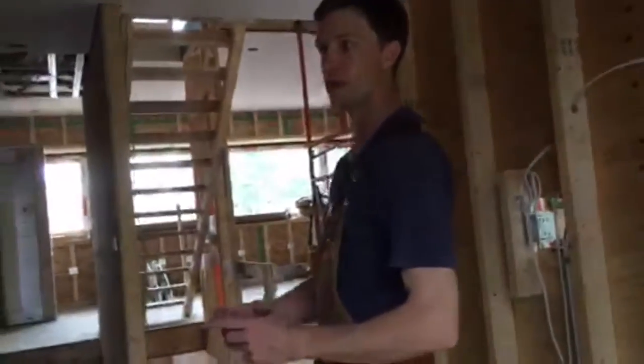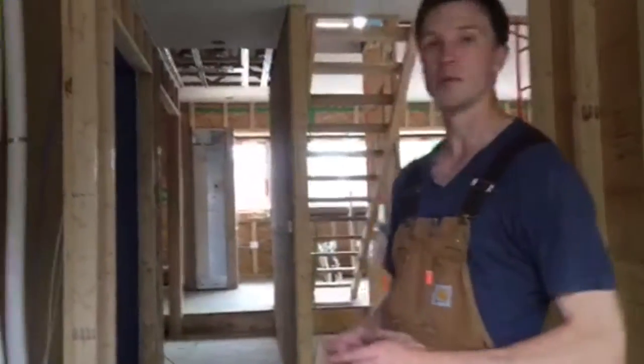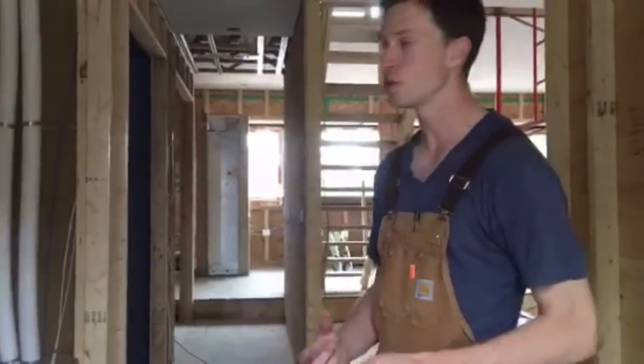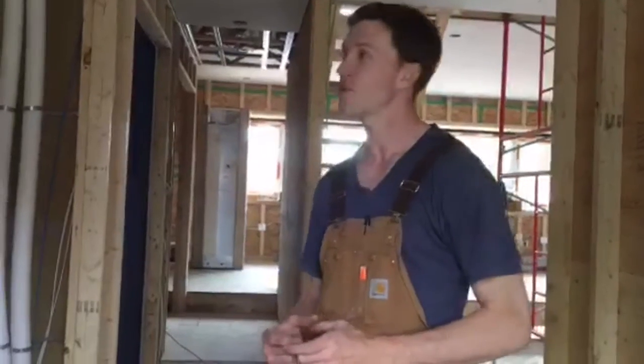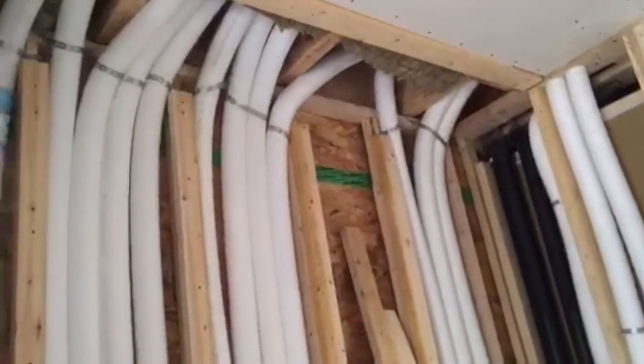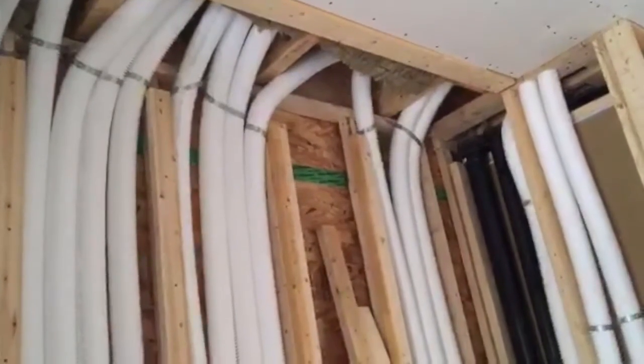It's starting to take shape nicely up here. You can see all of the flex duct work for the HRV system running through the wall cavities. It fits nicely in a 2x4 wall. We did have to use a 3-inch hole saw to cut it out everywhere it went through the 2x4. Something to know if you're installing this system in the future is that 2x4 walls don't have much wood left in them after you've run this duct through them. So if you're ever going horizontally through a wall, a 2x6 might work better. Something to know for next time.